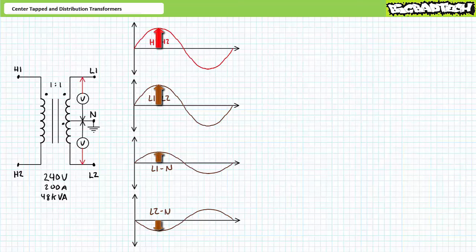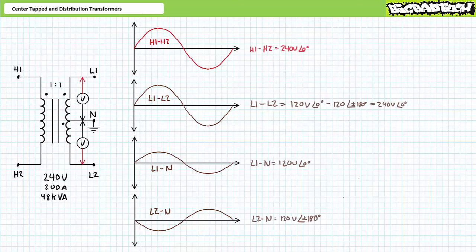L1 also peaks positively and L2 valleys negatively. With ground as the established reference, L1 and L2 are equal in magnitude yet perfectly out of phase with one another. If we were to express these voltages as phasor equivalents, H1 to H2 would be 240 volts at an angle of 0 degrees. L1 to neutral would be 120 volts at an angle of 0 degrees. L2 to neutral would be 120 volts at either positive or negative 180 degrees.